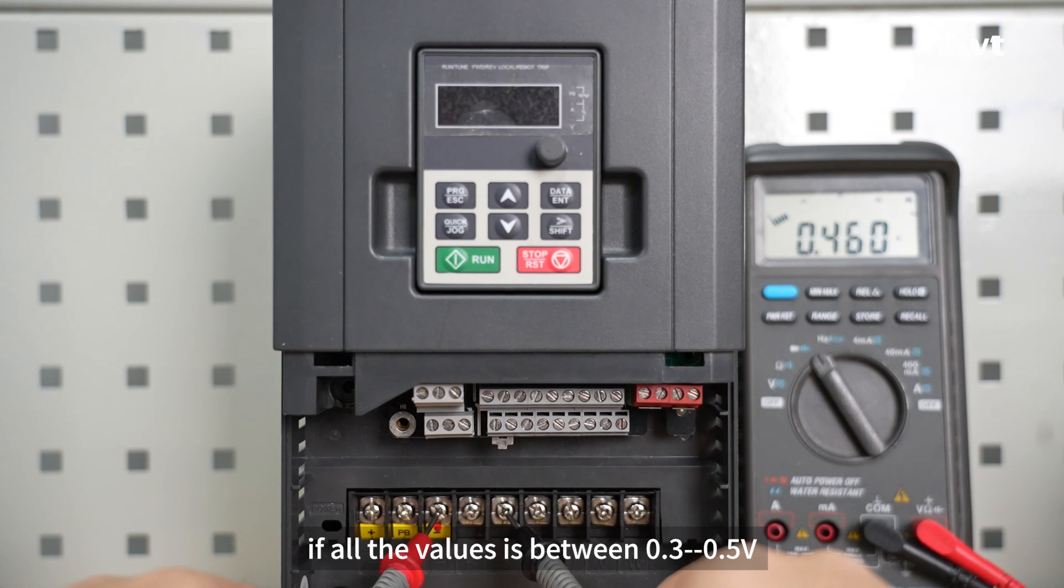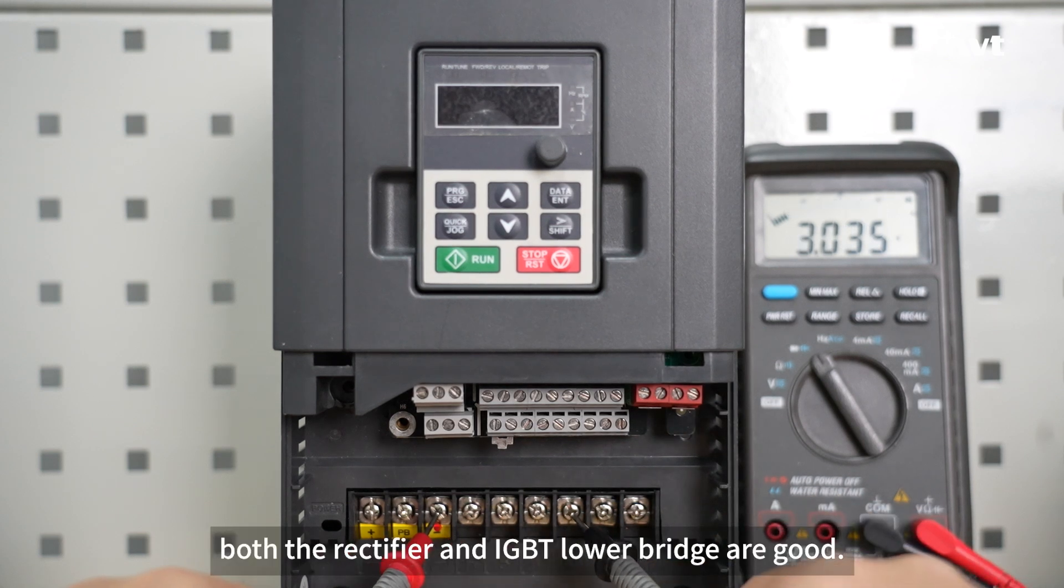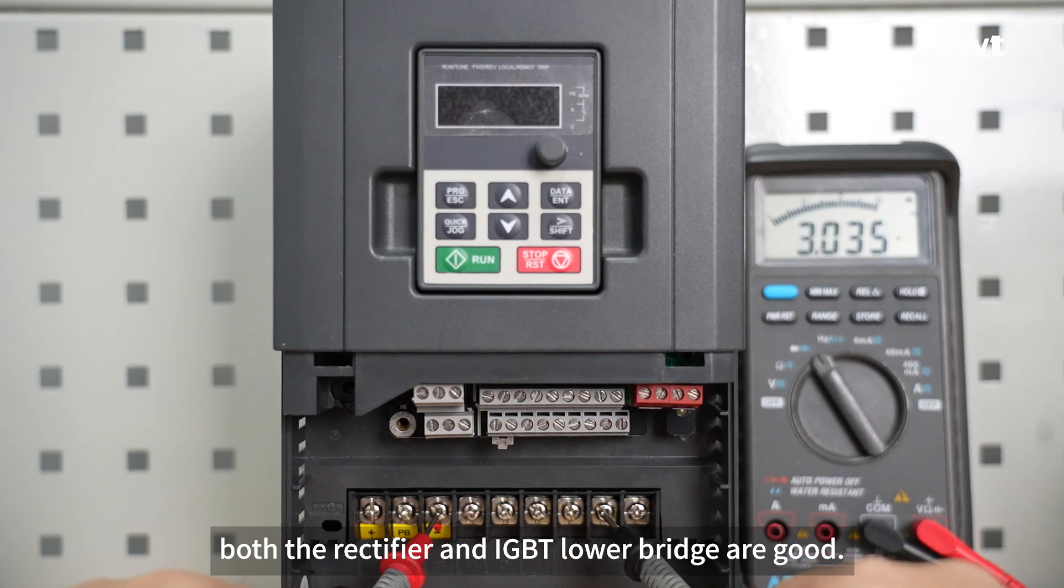If all the values are between 0.3 to 0.5 volts, both the rectifier and IGBT lower bridge are good.